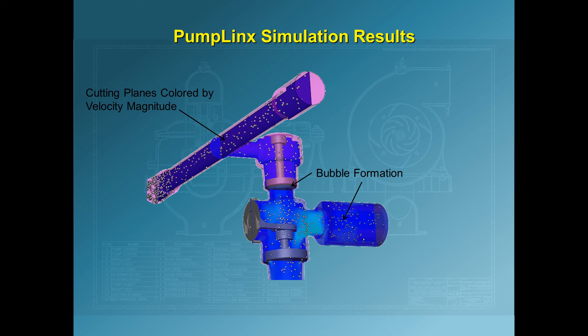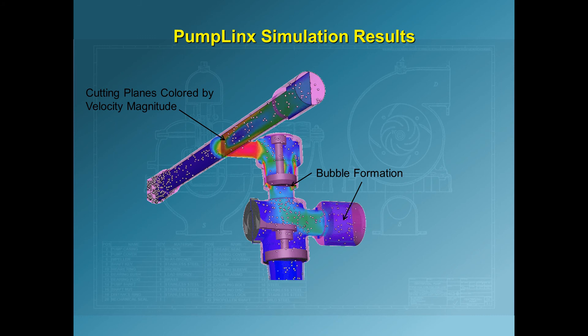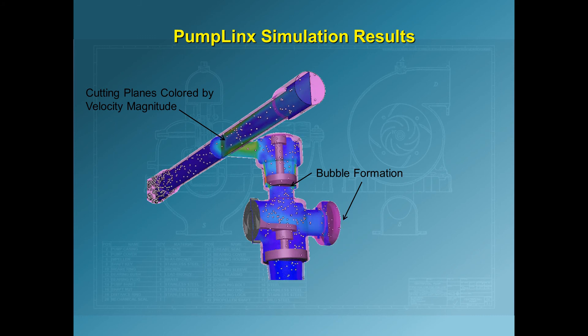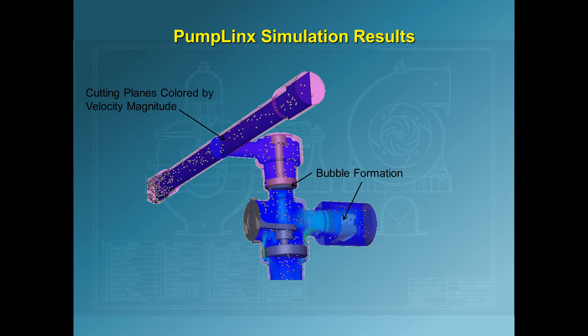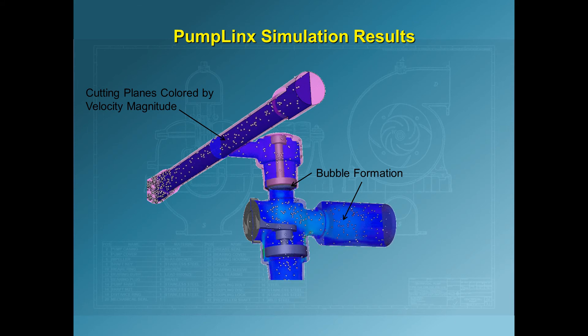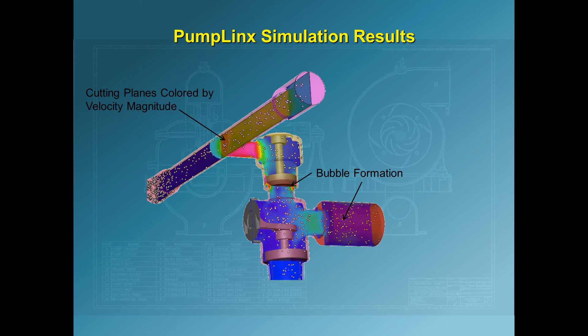Here we see the flow field colored by velocity magnitude, seeded with massless particles for flow visualization. Bubbles are formed in the piston chamber and under the valve outlet due to the pressure drop during the expansion stroke as the fluid opens the inlet valve at the bottom.